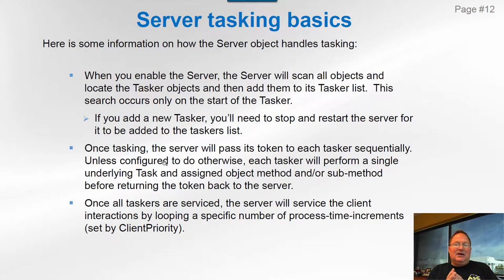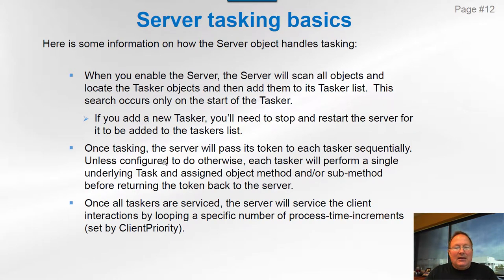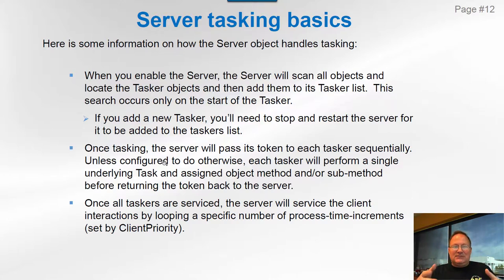Server tasking basics: when you enable the server, it scans all objects within the configuration, locates all the tasker objects, and assembles them into a list — remembering where all the taskers are. From that point on, it starts token passing to all taskers and to client interactions. This means that if you add a tasker object to your configuration while the server is on, it won't be recognized because that new tasker won't be in the list. So if you add a tasker and want it to start tasking, you have to turn the server off and back on.